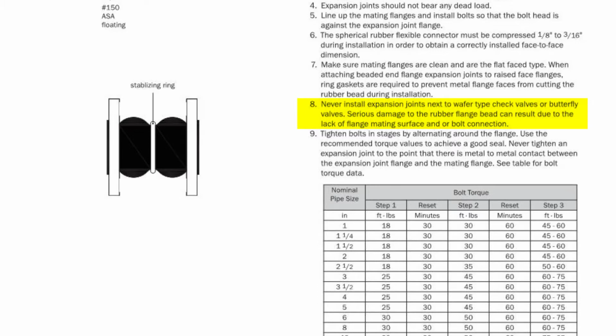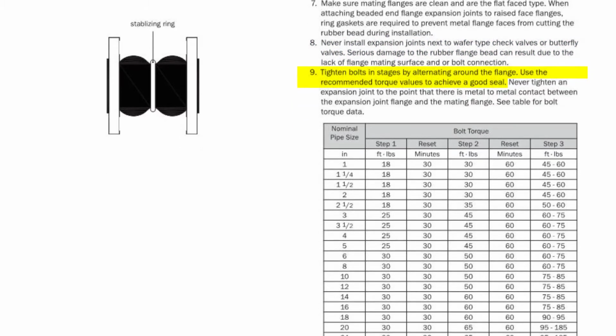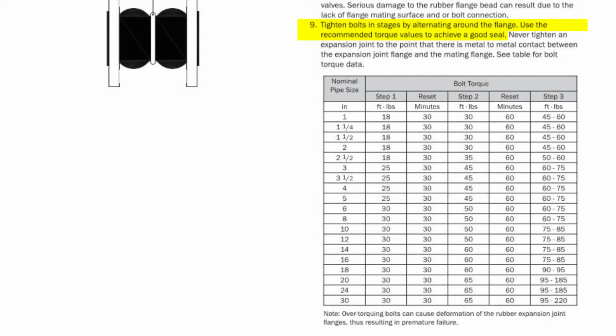Since the joint is made of a compressible material, the installation requires a few steps of tightening the flange bolts to ensure a proper seal on either end. The bolt torque table here gives appropriate values for torque and minimum wait times before proceeding to the next round of tightening. Tightening should be done in a star pattern or alternating around the ring. Final torque values need to be within the range shown here. For the joint we just looked at, the torque values for all bolts should be between 60 and 75 foot-pounds as measured using a torque wrench.